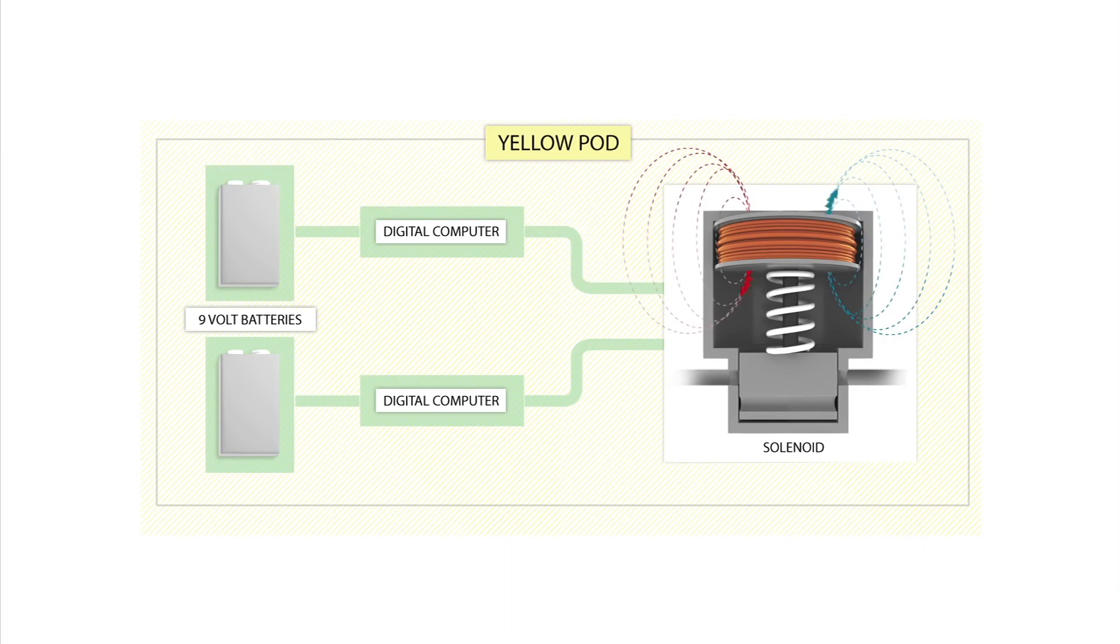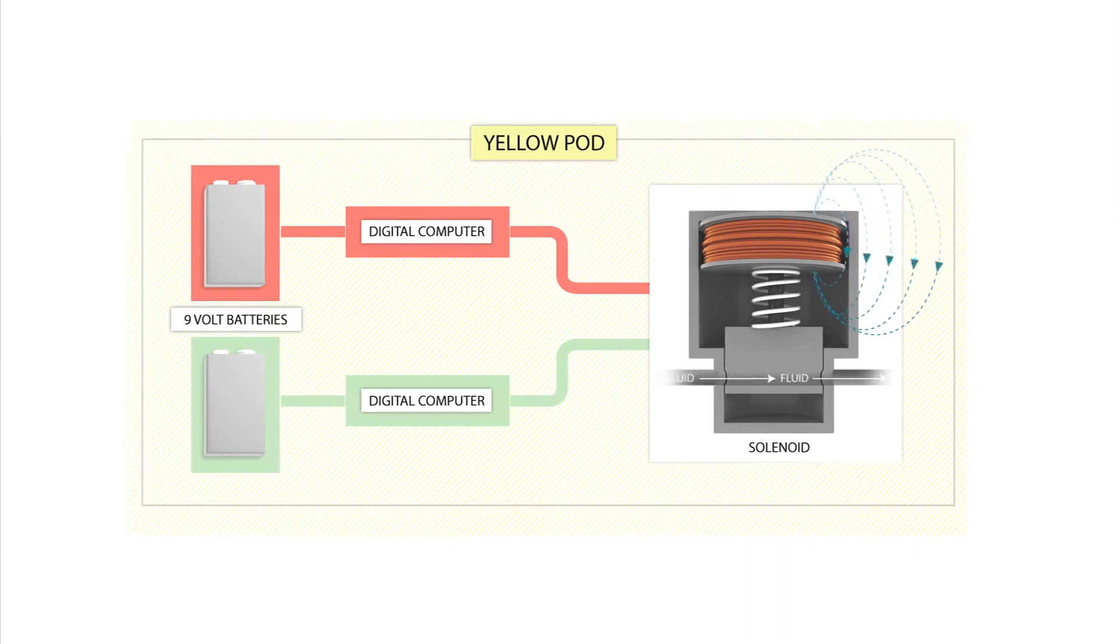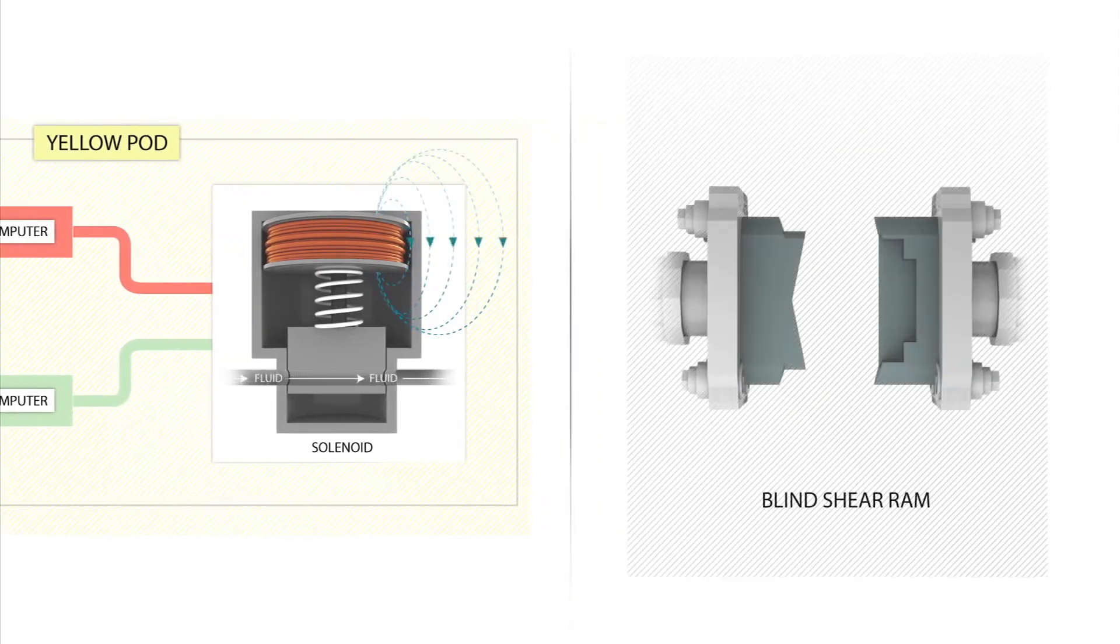Had both coils of the miswired solenoid valve been energized, the two coils would have generated opposing forces on the valve. The solenoid valve would have remained closed, and the blind shear ram would never have been closed. However, the failed battery rendered one coil inoperable, and most likely allowed the other coil to open the solenoid valve by itself. This, in turn, initiated closure of the blind shear ram.